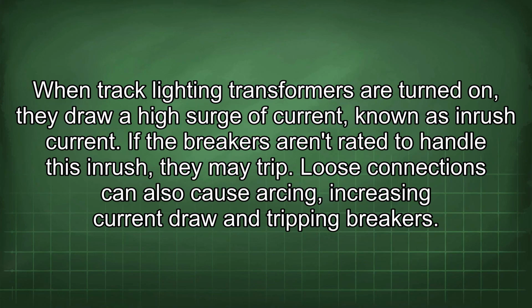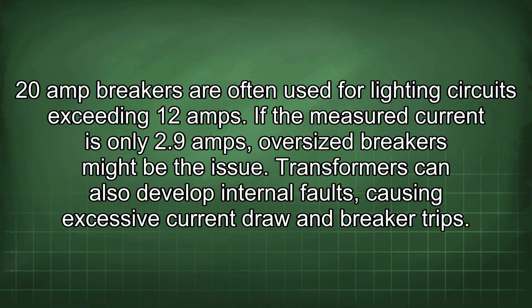When track lighting transformers are turned on, they draw a high surge of current, known as inrush current. If the breakers aren't rated to handle this inrush, they may trip. Loose connections can also cause arcing, increasing current draw and tripping breakers. 20 amp breakers are often used for lighting circuits exceeding 12 amps. If the measured current is only 2.9 amps, oversized breakers might be the issue.